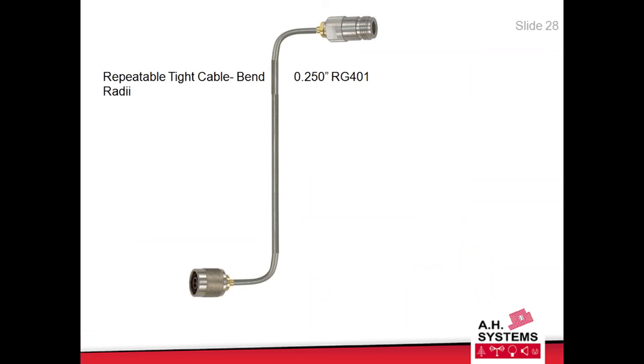There's this semi-rigid cable, it's readily available. Putting the connectors really aren't too hard, but you do need a good size soldering iron. And there's your preformed, very repeatable setup. I mean, you mark these things up and you say, for this test, use this, and you take a picture of how the guy who's doing the test setup has to run that cable. Very repeatable and tight cable bends.